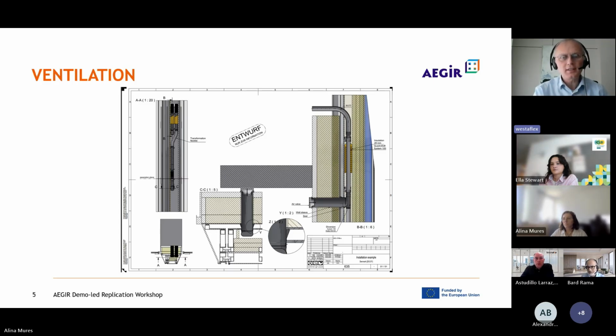Especially on the right hand side, the section marked BB, you will see the very tricky assembly of the prefabricated facade, because you have to assemble the horizontal ducts and the vertical ducts during the assembly of the facade. So you have to be very precise putting the ductwork into the prefabricated facade, and then when you assemble it, you have to connect the horizontal part to the vertical part within the prefabricated facade element.